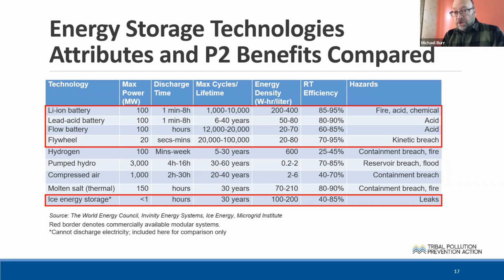The more you discharge them, and the lower you discharge them—you can't discharge a lithium battery all the way down to zero charge or you'll ruin it very quickly. For energy storage batteries, the rule is not below about 30%, depending on the type of system. So you may have theoretically 100 kilowatt hours of capacity, but in principle you can't actually discharge all of that. That's a factor in calculating your capacity and the resources you're putting in to start with.